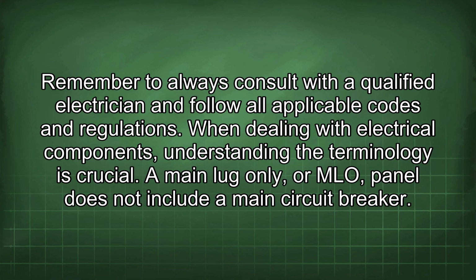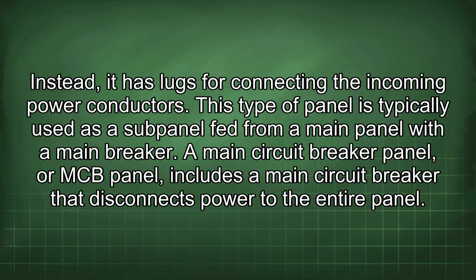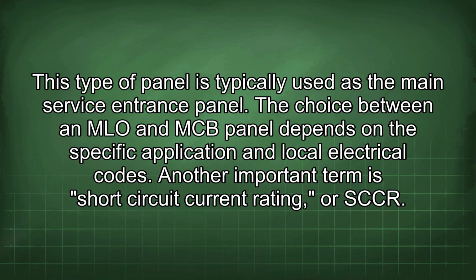When dealing with electrical components, understanding the terminology is crucial. A main lug only, or MLO, panel does not include a main circuit breaker. Instead, it has lugs for connecting the incoming power conductors. This type of panel is typically used as a subpanel fed from a main panel with a main breaker. A main circuit breaker panel, or MCB panel, includes a main circuit breaker that disconnects power to the entire panel. This type of panel is typically used as the main service entrance panel. The choice between an MLO and MCB panel depends on the specific application and local electrical codes.